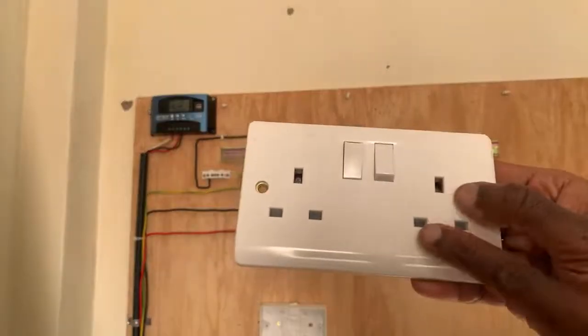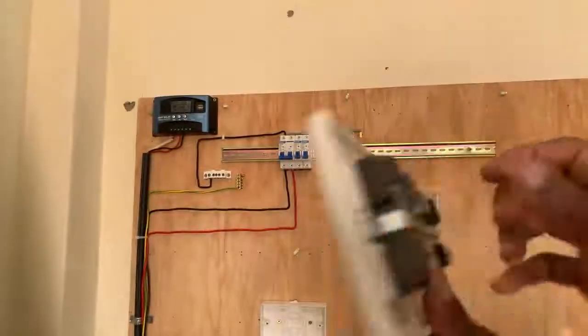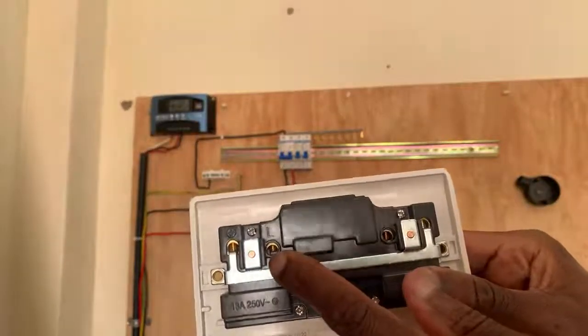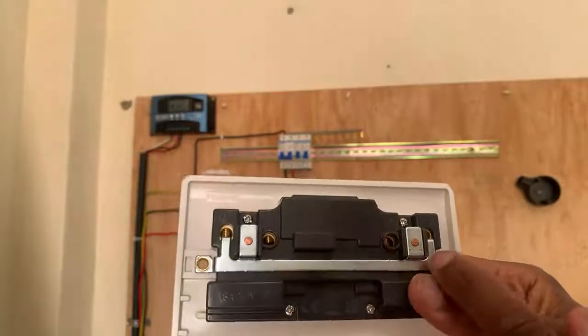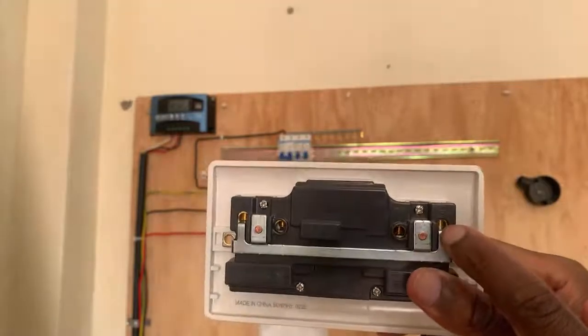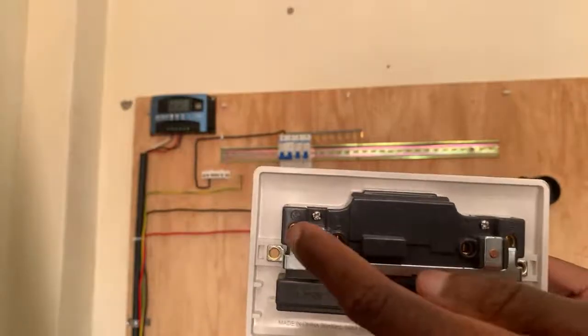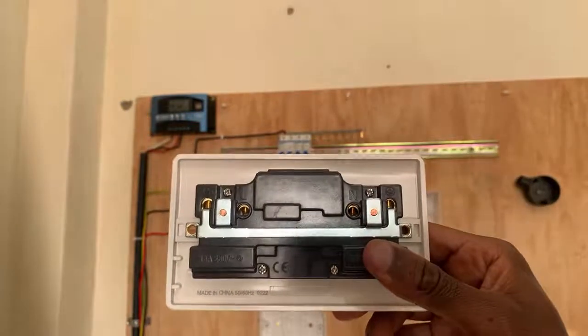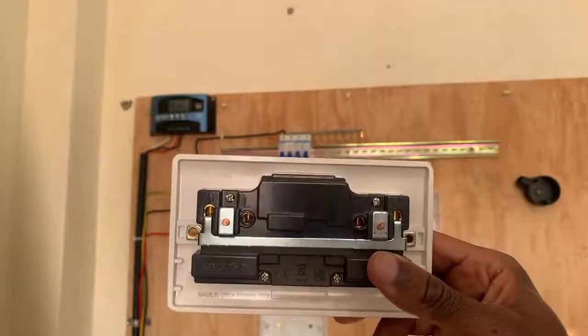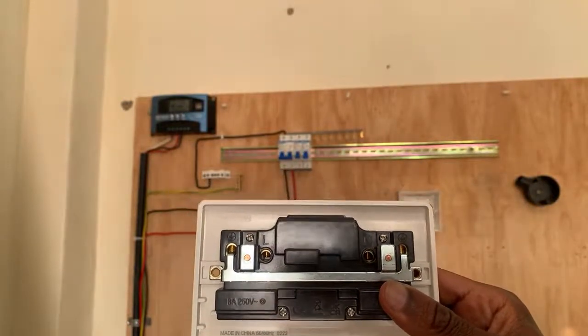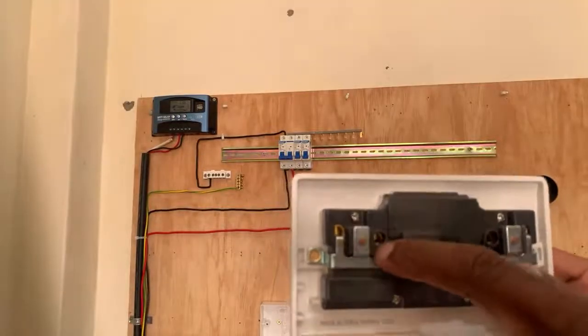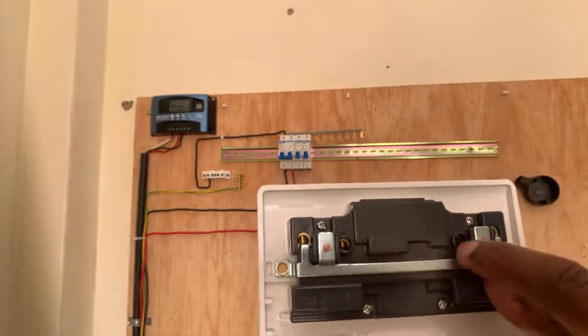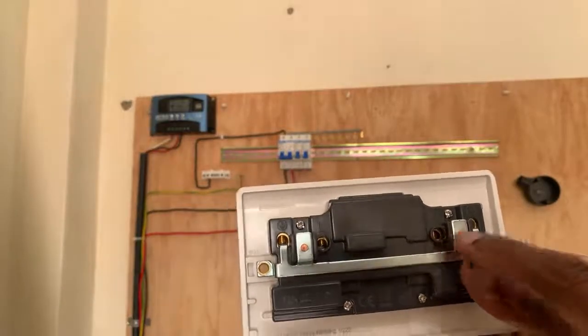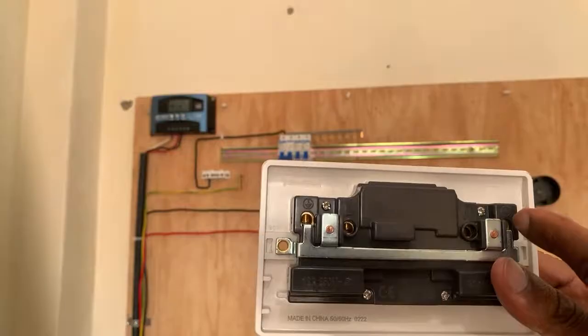The similarity between the twin socket and the single socket is that they all have the connection for the live, the neutral (only one connection), and the earth connection. For the twin, you have two connections for the earth, but for the single, you have only one. So the phase will be connected to L, the neutral to N, and the earth to either of those particular points.